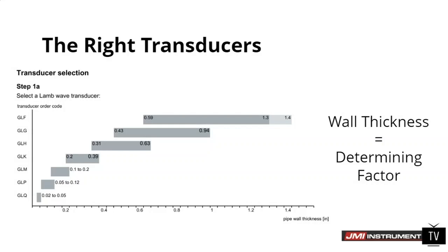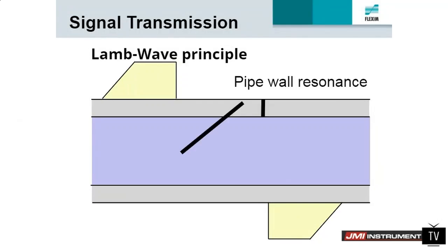This is Lamb wave, so this is what we're using to resonate this signal across. But we're resonating the signal across to give us a better chance of getting through this really light, low-density medium here. Typically, we like to have about 80 psi of pressure in a metal pipe. Depending on the OD of the pipe, it has a lot to do with that as well. The farther the wave has to travel, the more density that we need in order to get a signal through the medium.